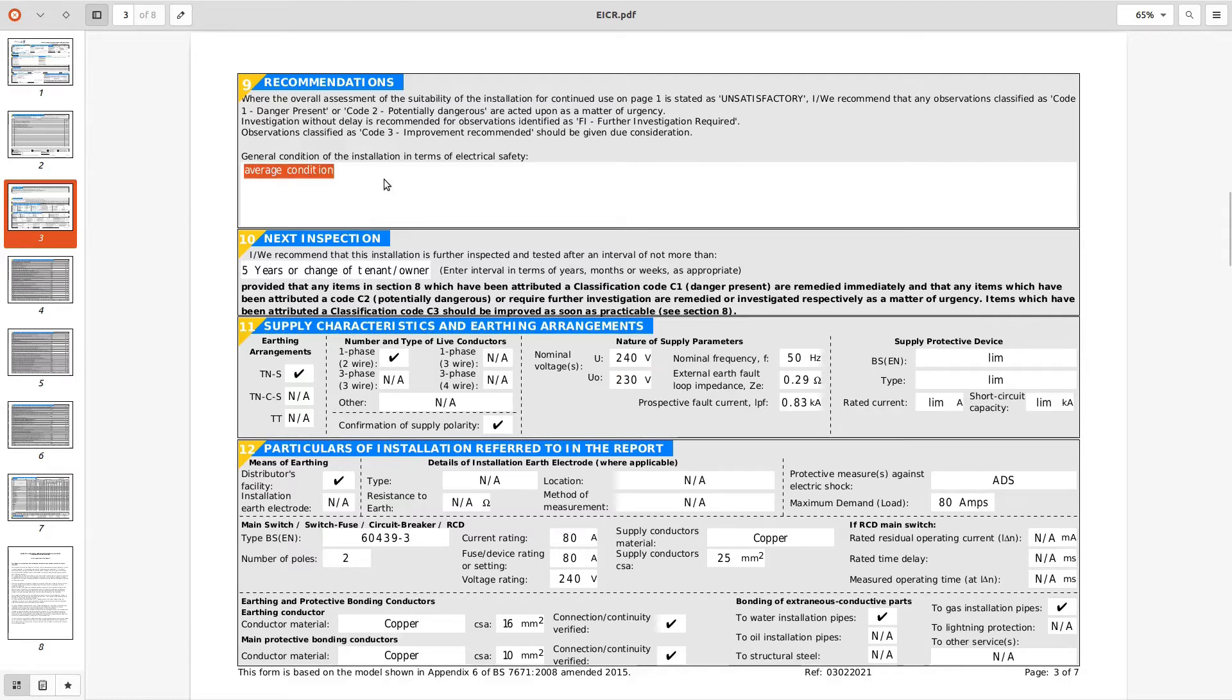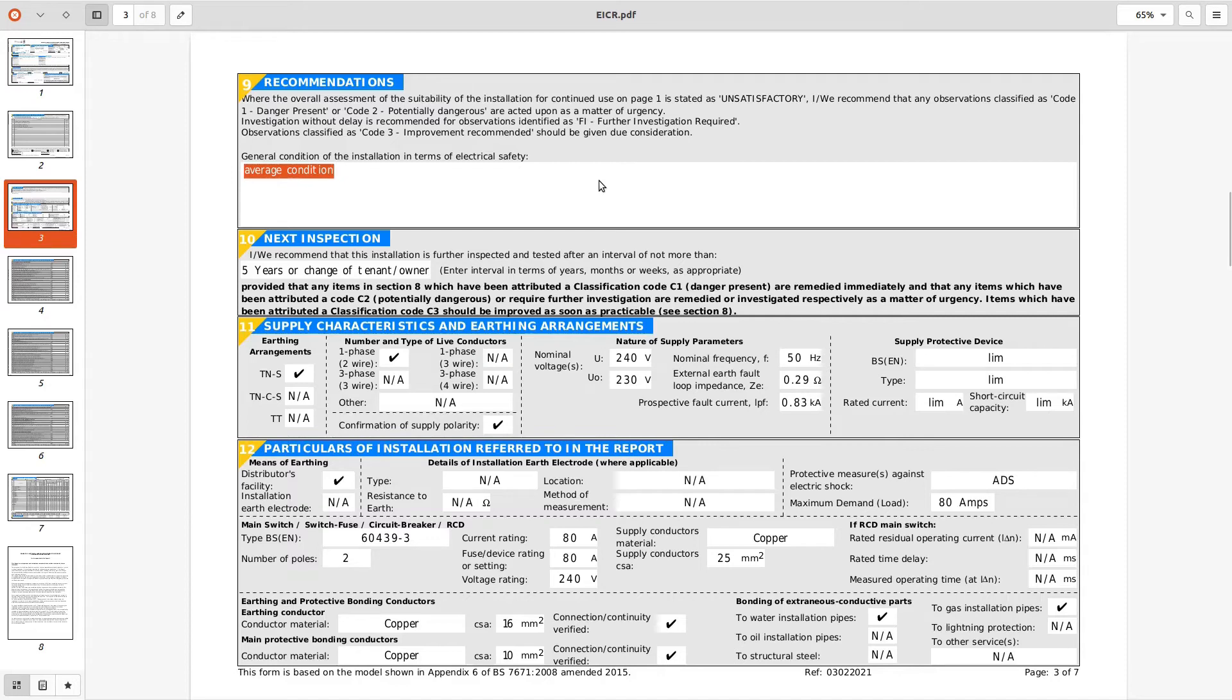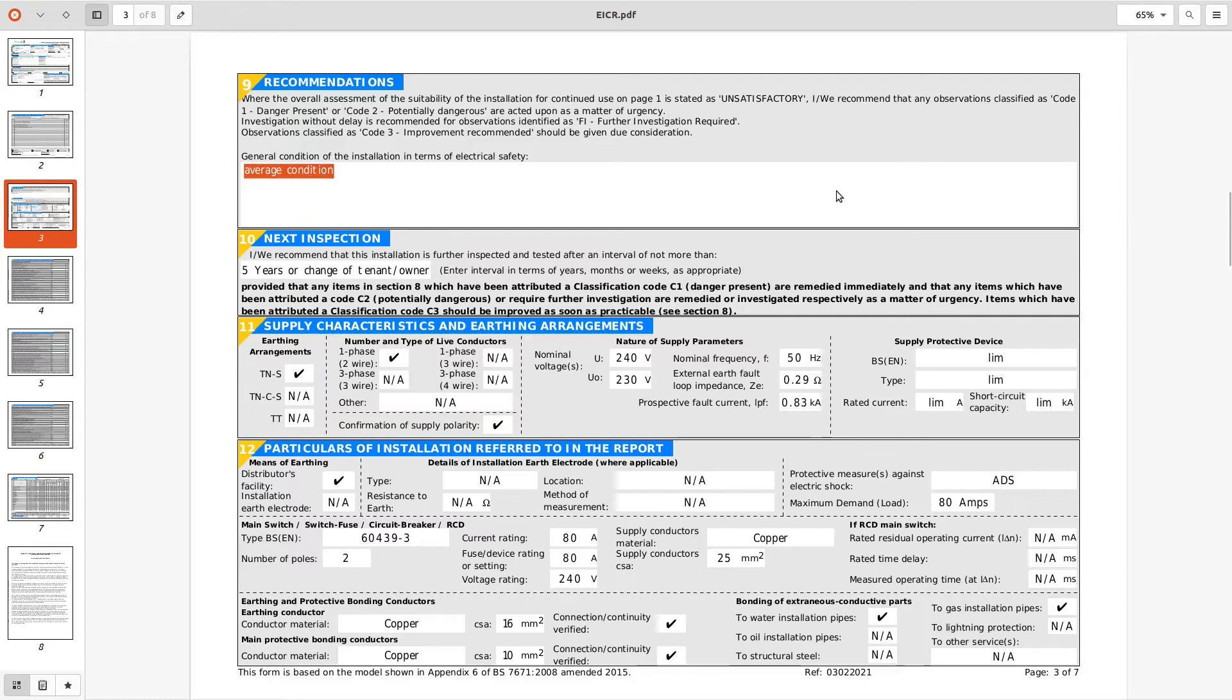So you need to be putting a bit more than average condition. Put that it's a split load board, RCD protection afforded for circuits whatever, these bondings not satisfactory or whatever you think, good insulation resistance readings. You need to be putting a bit more bump into here to give almost a lay person as to how it is. Average condition means nothing to me.